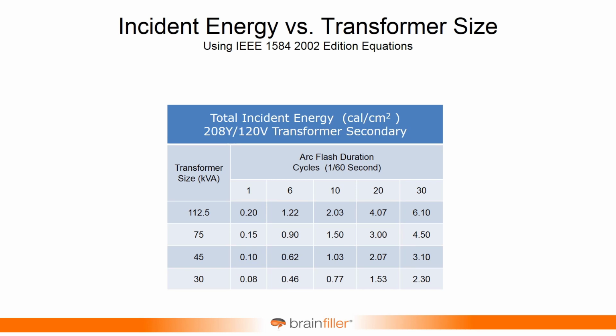I ran some numbers based on the 2002 edition of IEEE 1584, looking at typical transformer sizes and a pretty typical impedance, and at the incident energy based on 1 cycle, 6 cycles, 10 cycles, 20, and 30 cycles. With a 112.5 kVA transformer, you cross over that magical 1.2 calories per square centimeter threshold where protection is going to be required. It's often referred to as the onset of a second-degree burn. You cross over that at 6 cycles, so you'd have to have a pretty fast extinction. For a 75 kVA, it's going to take a little more duration, and you can see the trend, 45 kVA, 30 kVA. So that's a little bit of what drove the language from the 2002 edition of the standard.